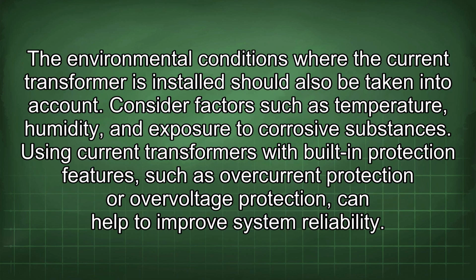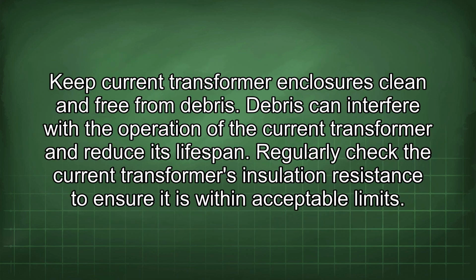The environmental conditions where the current transformer is installed should also be taken into account. Consider factors such as temperature, humidity, and exposure to corrosive substances. Using current transformers with built-in protection features, such as overcurrent protection or overvoltage protection, can help to improve system reliability. Keep current transformer enclosures clean and free from debris. Debris can interfere with the operation of the current transformer and reduce its lifespan.